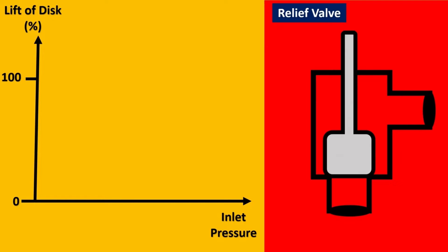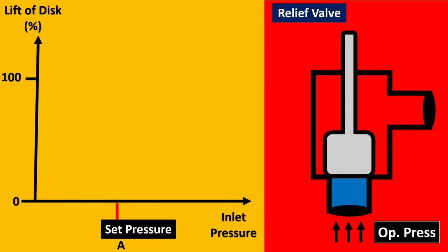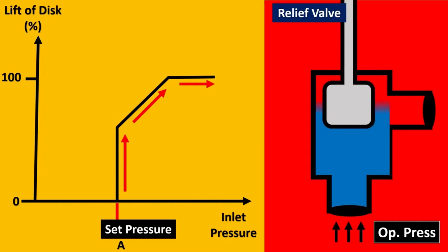Imagine we plot inlet pressure on the x-axis and lift percentage of the disc on the y-axis for a relief valve. We keep the range from 0 to 100 percent. As the operating pressure hits the disc but does not reach the set pressure — let's call it point A — the disc will never open. Once the set pressure is reached, the disc starts opening to some percentage and eventually reaches 100 percent, relieving all pressure to the outlet.